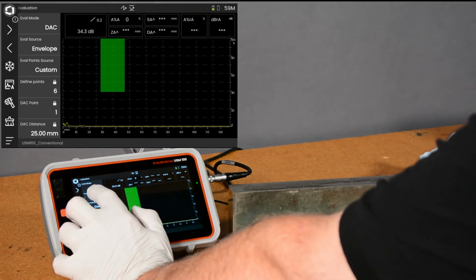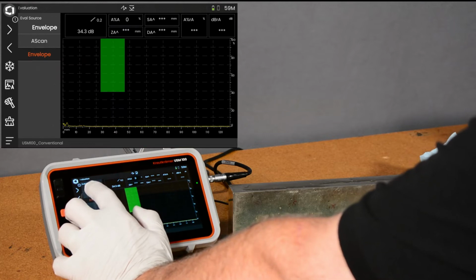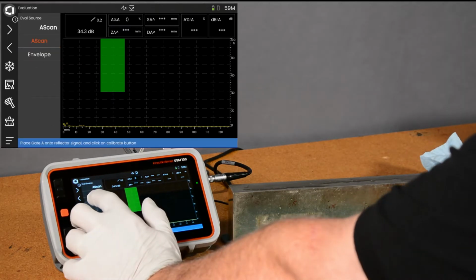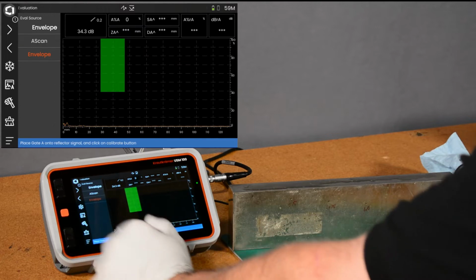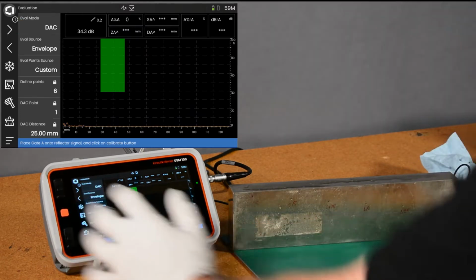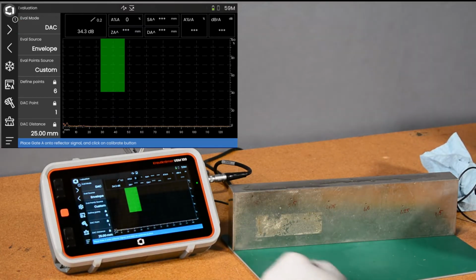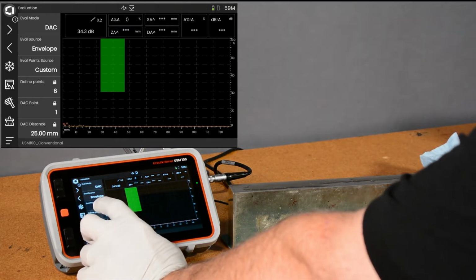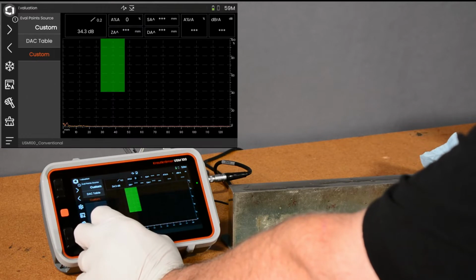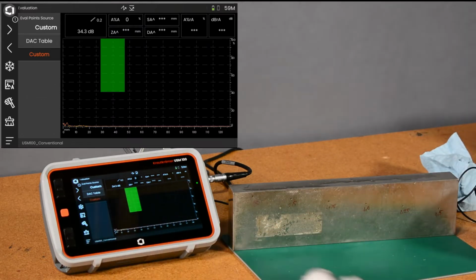I have a choice of either calibrating using my live A scan or using the envelope feature. I'm going to choose envelope because that makes it much easier to get peaked up on each one of my side drilled holes. The next choice I have is whether I want to use a pre-programmed table.